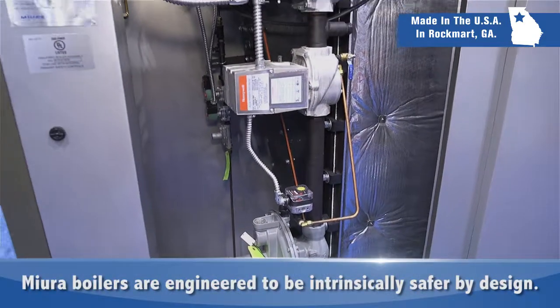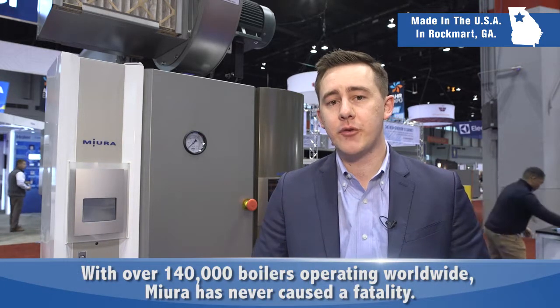Miura boilers are engineered to be intrinsically safe by design. Our low water content design contains about one-tenth the amount of water as a traditional fire tube, which means there's a lot less stored energy and a lot less potential for damage should the boiler ever fail. With our low water content design and advanced controls, Miura is proud to say with over 140,000 boilers operating worldwide, our boilers have never caused a fatality.